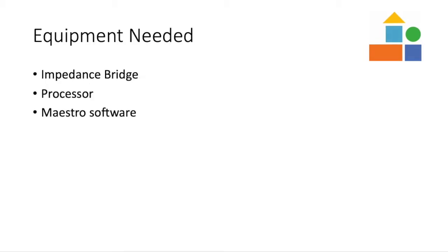The equipment needed to successfully obtain ESRT measurements are an impedance bridge with the ability to measure reflex threshold. For the purpose of this demonstration, a GSI TympStar Pro is being used, the patient's processor, and the MED-EL Maestro fitting software.